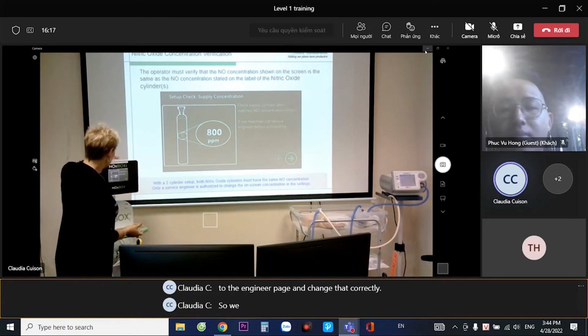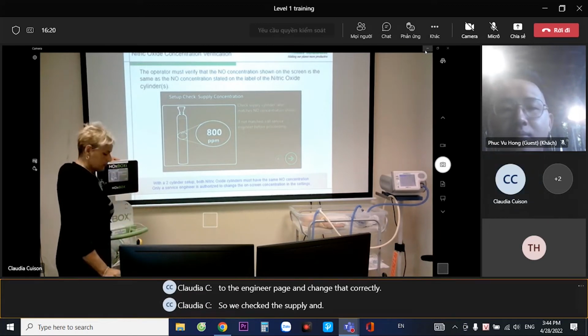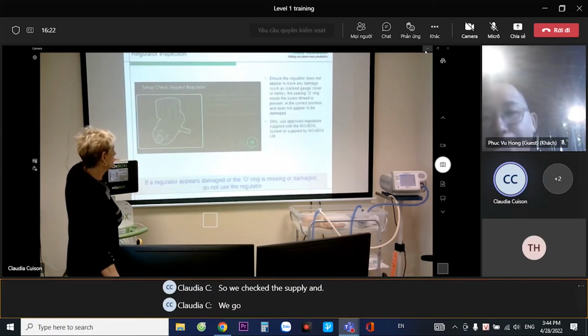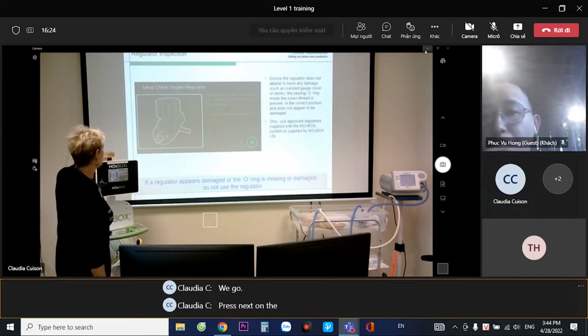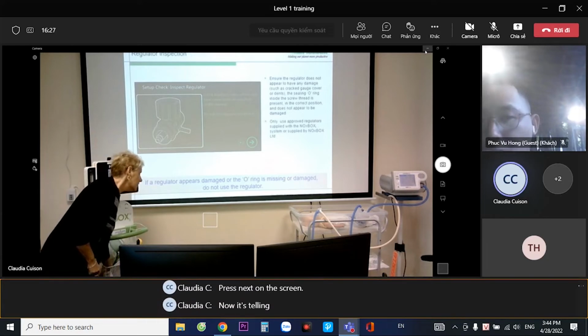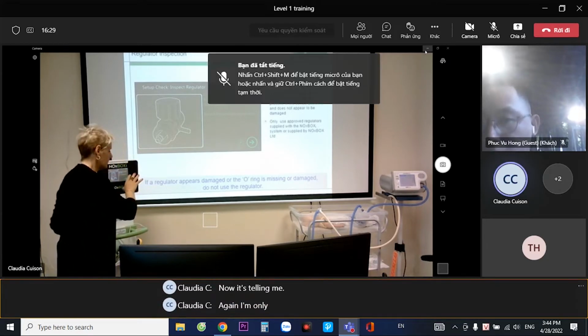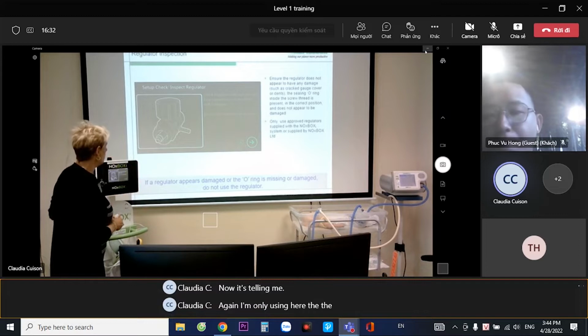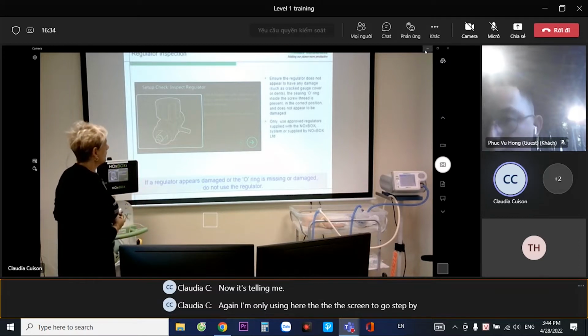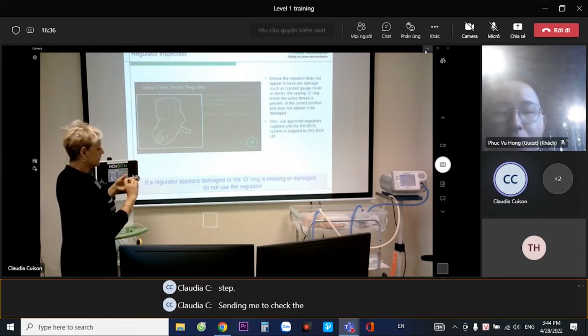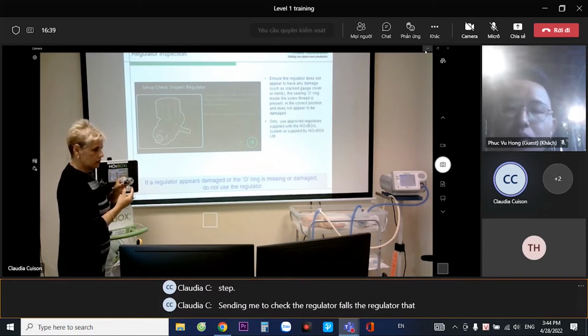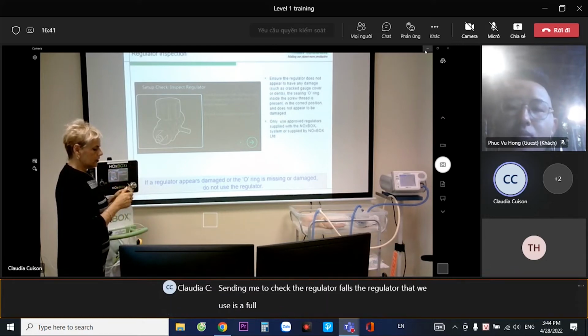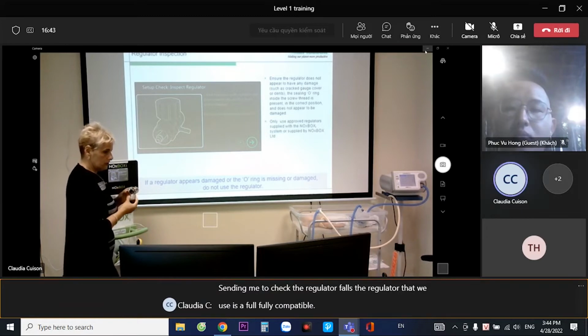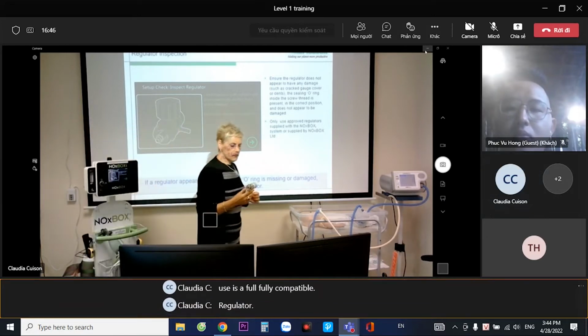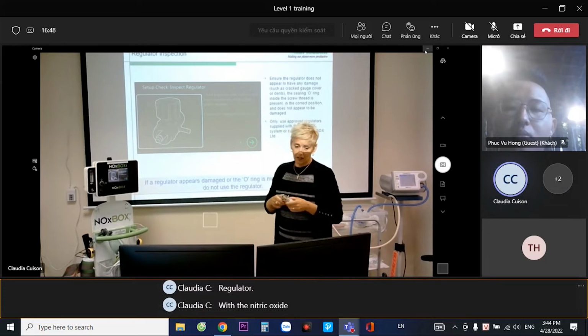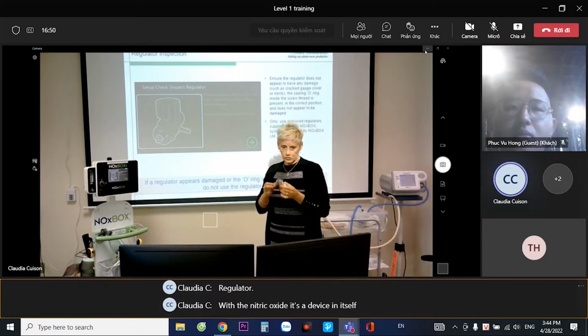So we check the supply and press next on the screen. Now it's telling me, again, I'm only using the screen to go step by step, to check the regulator valves. The regulator that we use is a fully compatible regulator with the nitric oxide. It's a device in itself. It's also a class 2B.